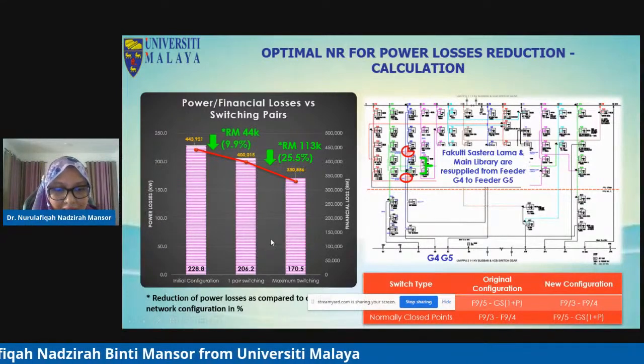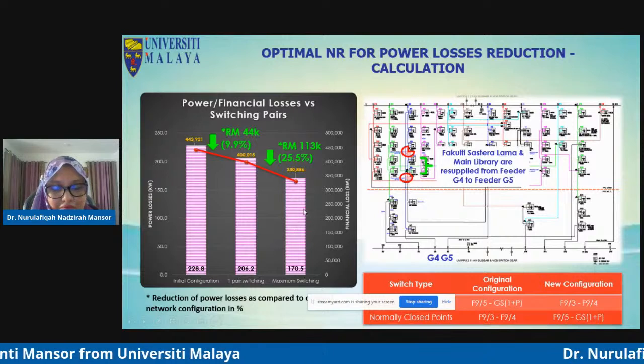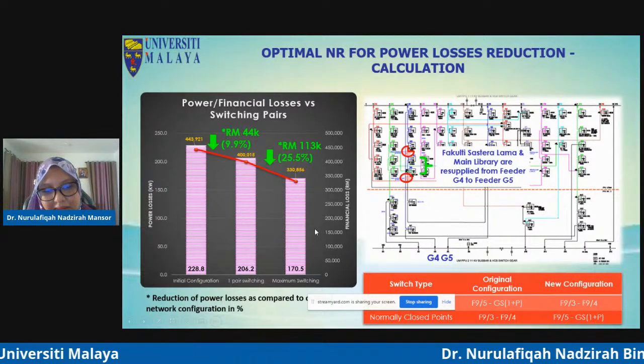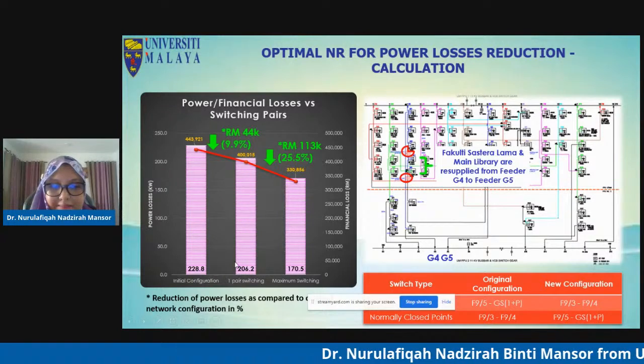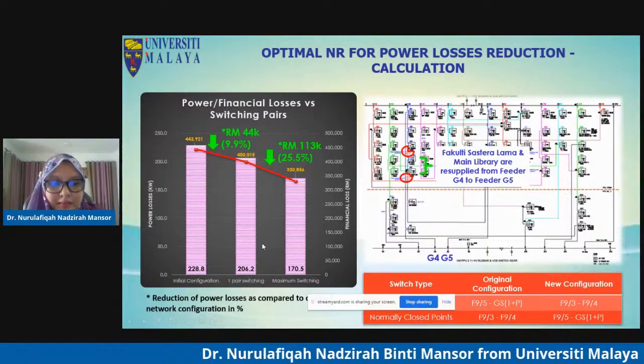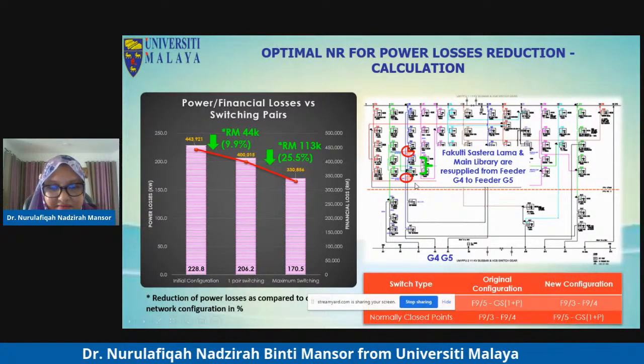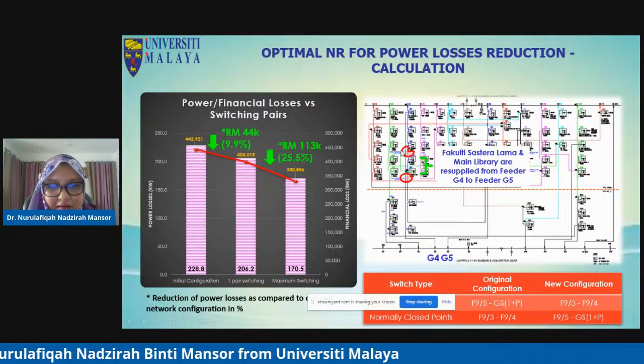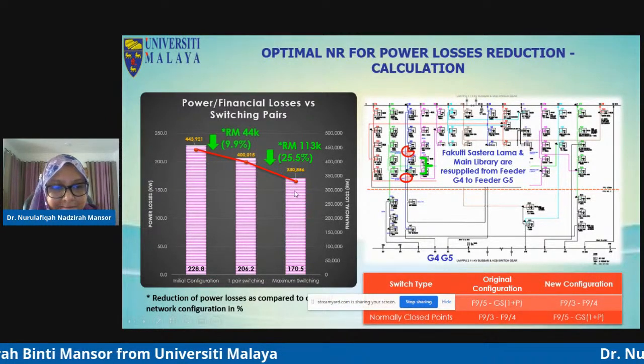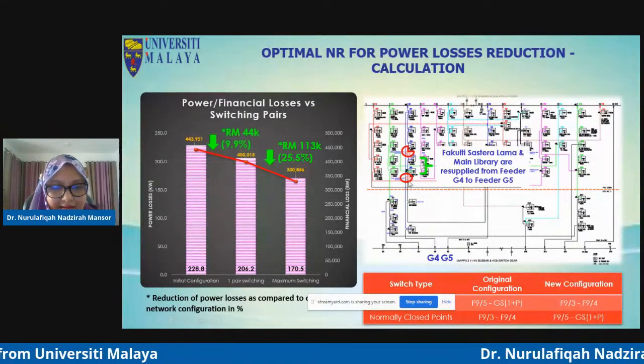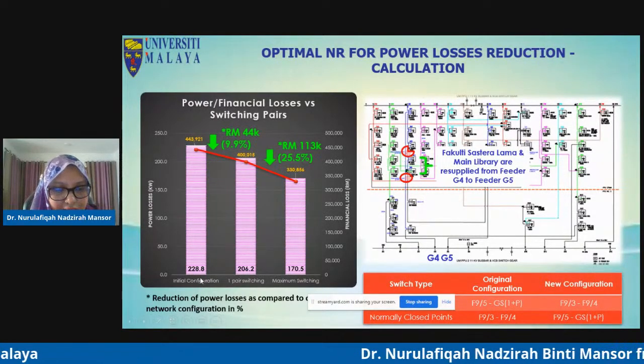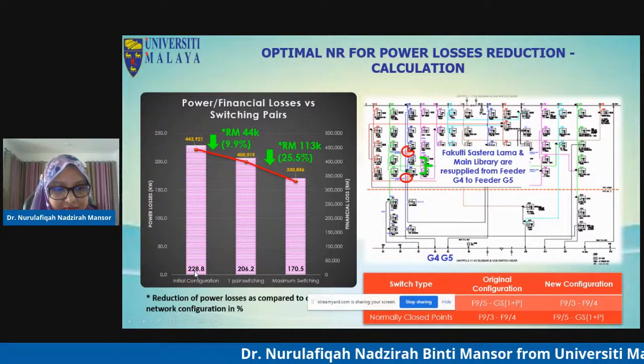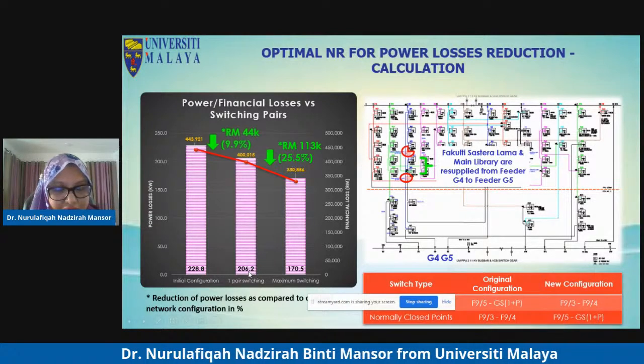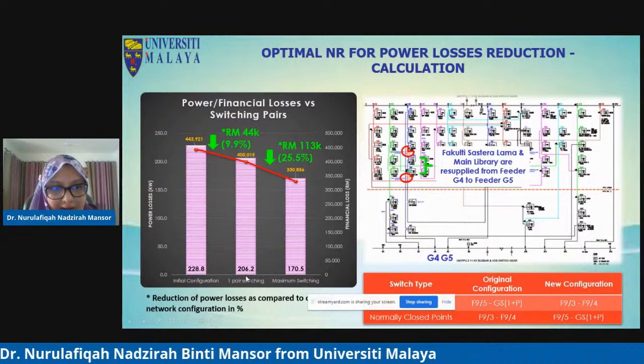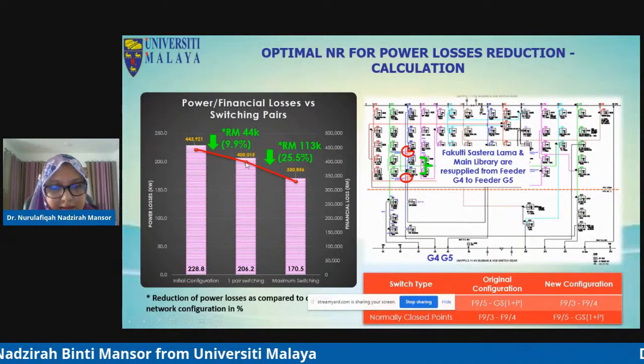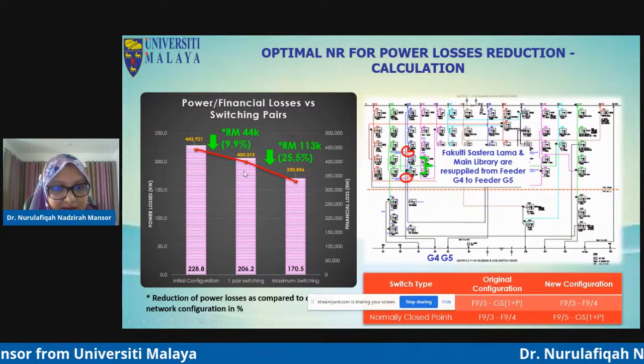So instead of going for the most optimal network configuration, we go for one pair switching, meaning we only change the switch status for one pair of switches. If we change that switch status, we could reduce the power losses from 229 to 206 kilowatt, and that translates to RM 400K financial loss.